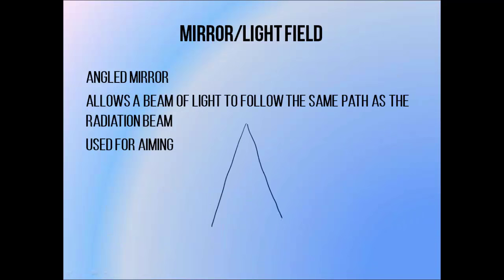Underneath the monitor chamber is a very thin angled mirror. We shine a light onto it from the side, which allows us to produce a beam of visible light that follows the same path as the radiation beam. Because we can't actually see the radiation and you don't want to be in the room when it's on, we use this light field instead to see where the radiation is going to hit the patient so we can point it at the right spot.